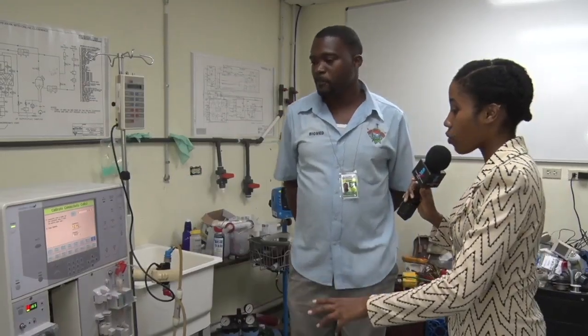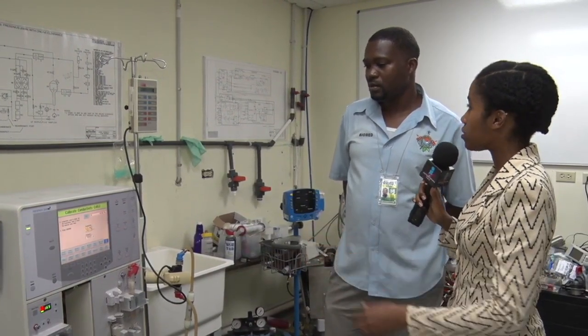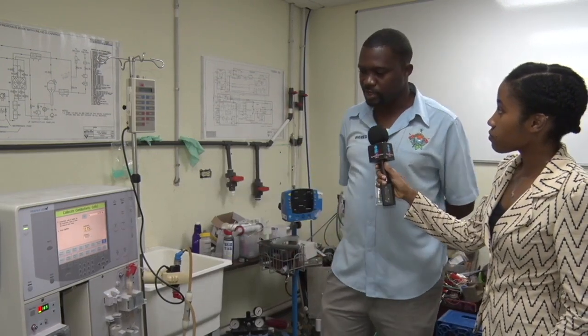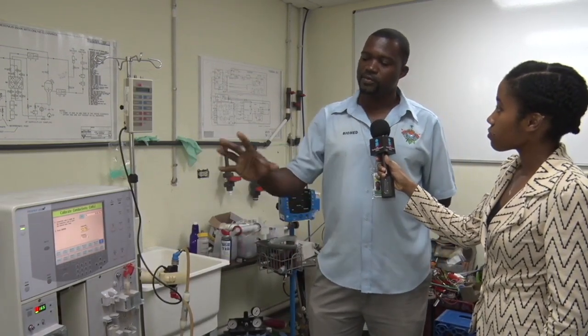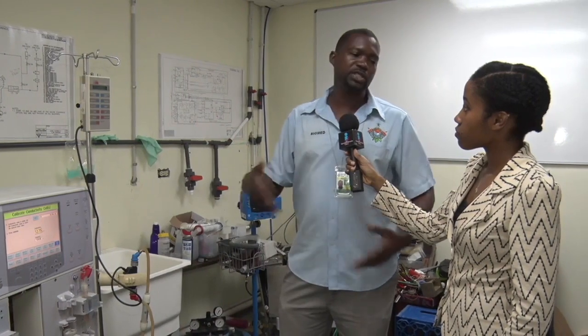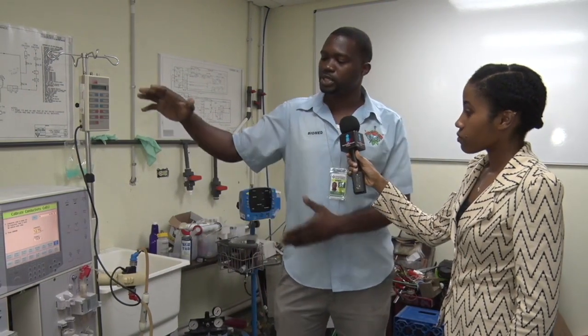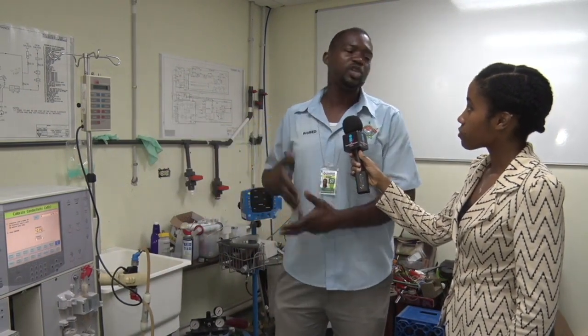So what is going on here — are you fixing this machine or doing some calibration or maintenance work on it? This is just a simple calibration on this machine. Sometimes if you have a machine just sitting in the department doing nothing, from day to day, we switch the machines. These are basically our backup machines. So if anything goes wrong on the floor, you can just switch and not slow down the process. Mr. Allen and I take pride in our work to make sure that every dialysis patient is comfortable. We always go beyond our call to make sure that everything is really up to standard.